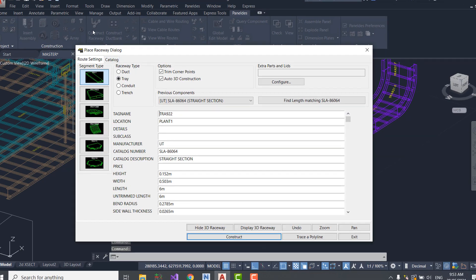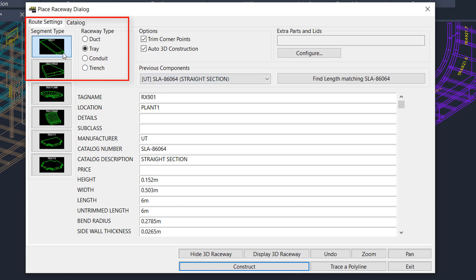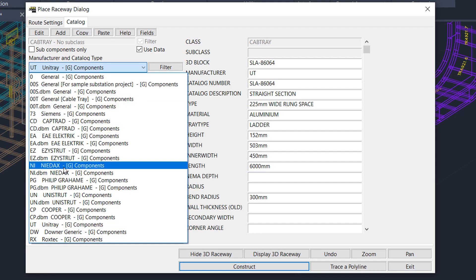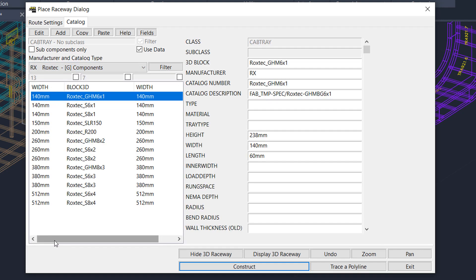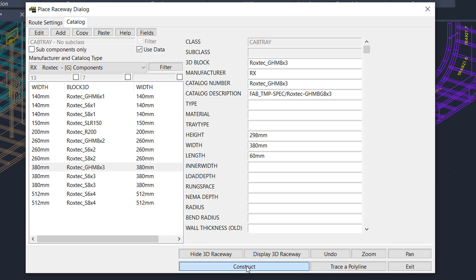I'm going to give the first transit a tag name. Transits are represented in Paneldes as a linear section of tray. On the catalog tab, you can select the exact component from a transit manufacturer. I'm going to choose a 3 frame 8 inch bolt in place transit. All of the dimensions are now loaded and any library blocks are linked. I just press the construct button to return to my CAD model and drag the transit into place.